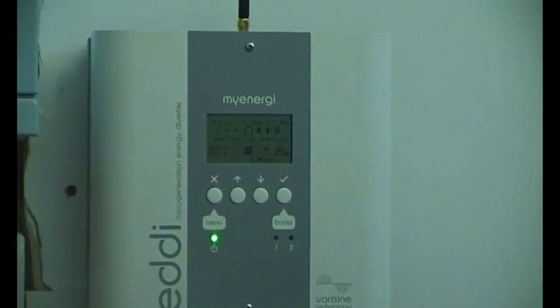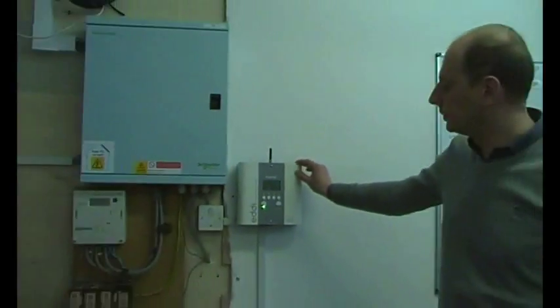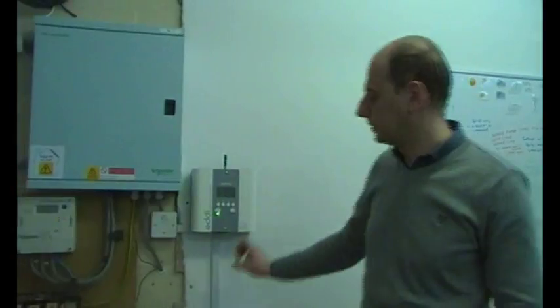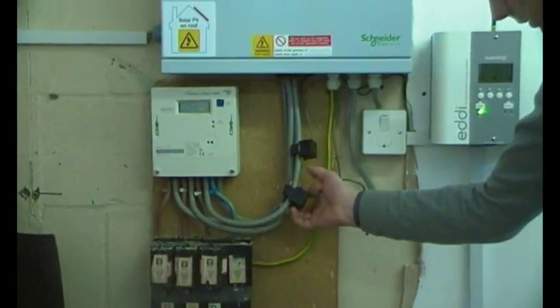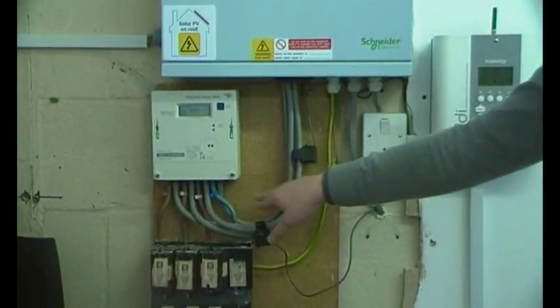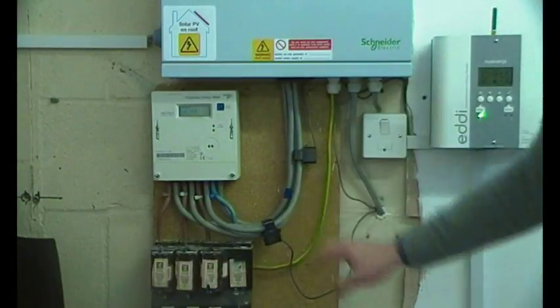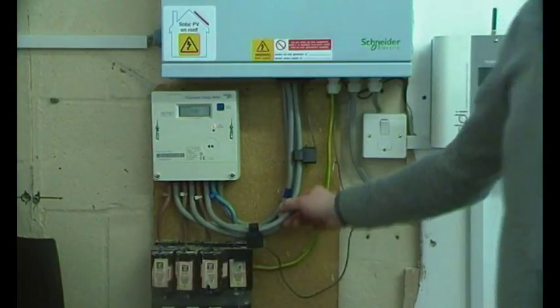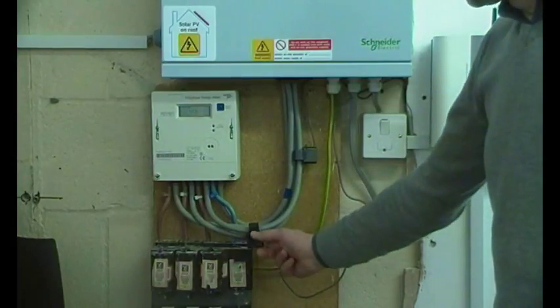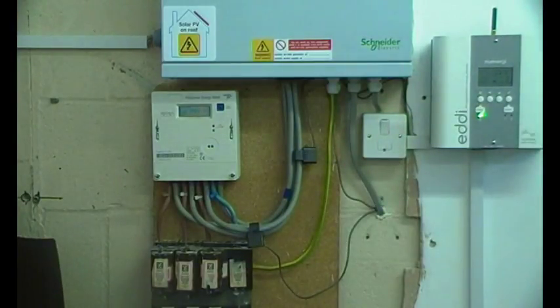Is that a wired sensor or wireless? It's either/or. At the moment this one is connected with a wired sensor on the live feed. This is three-phase because we're in a commercial building — in a domestic property you don't normally get three phase. It's just around one of the phases, which is the same phase the solar system is on. We've got a 3.68 kilowatt solar system.